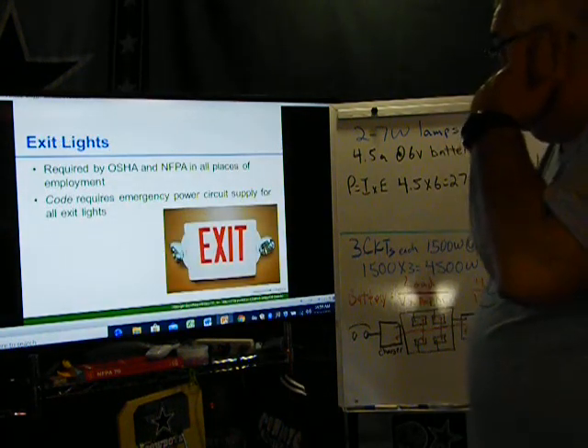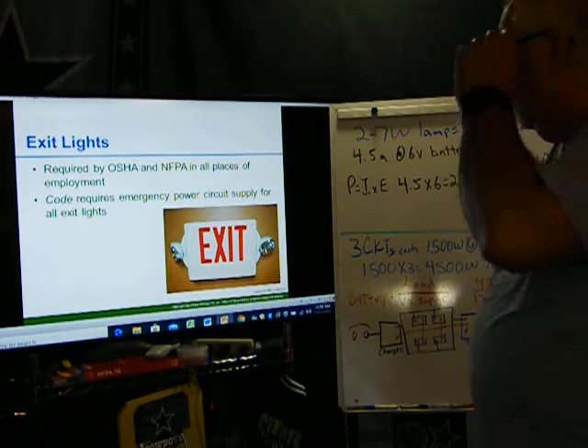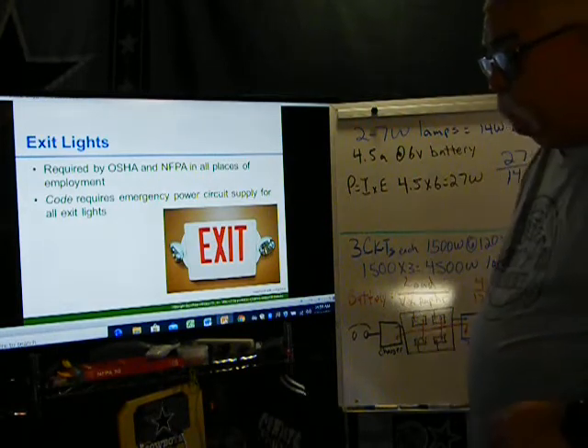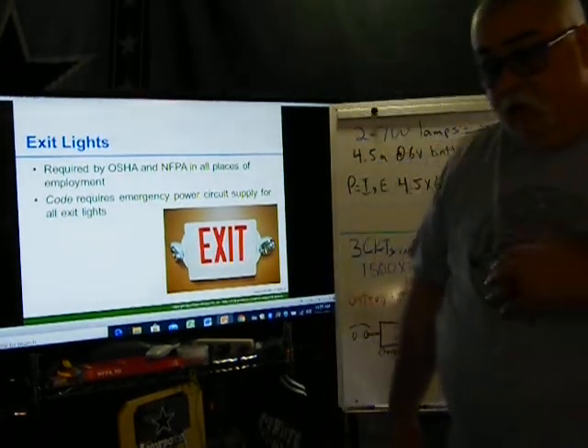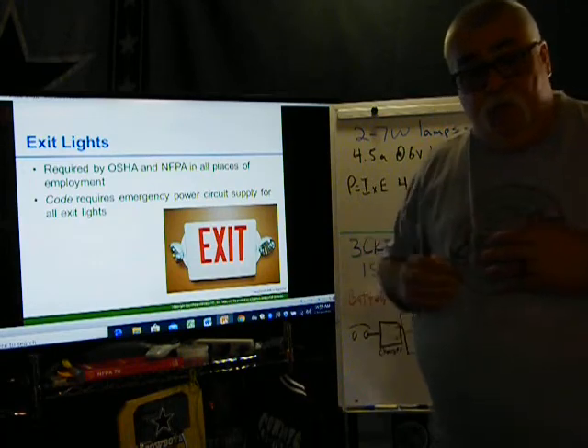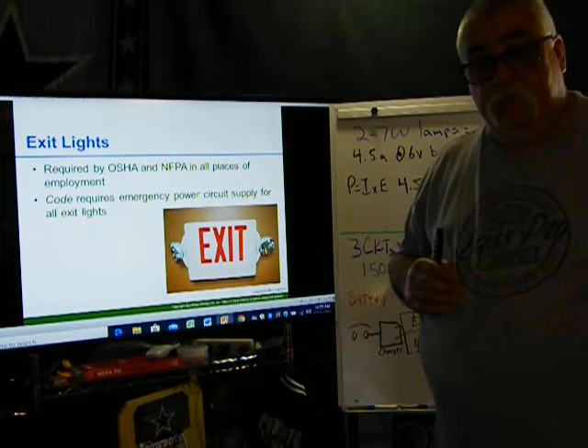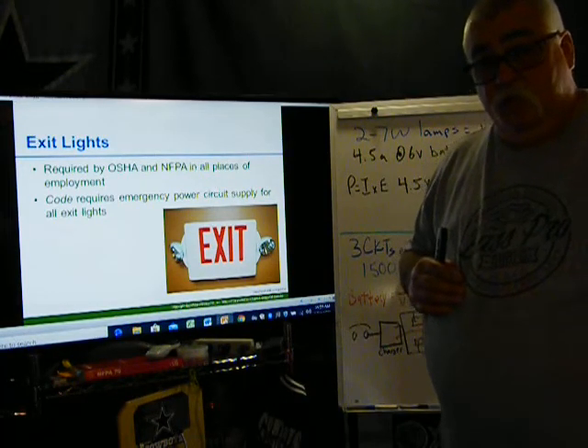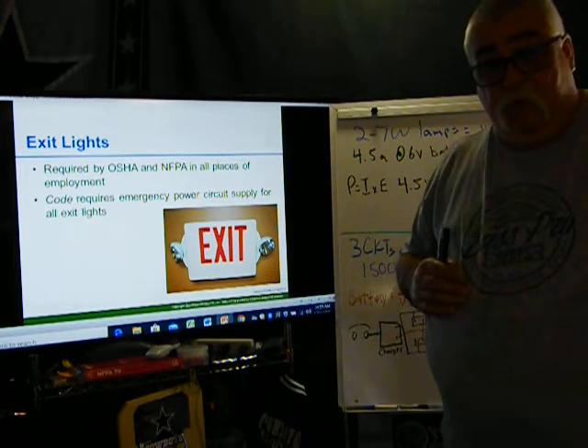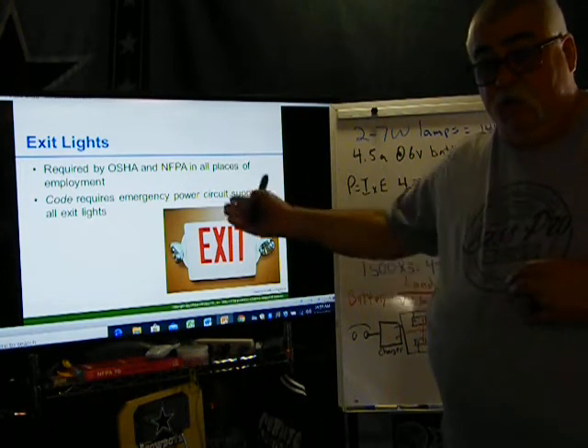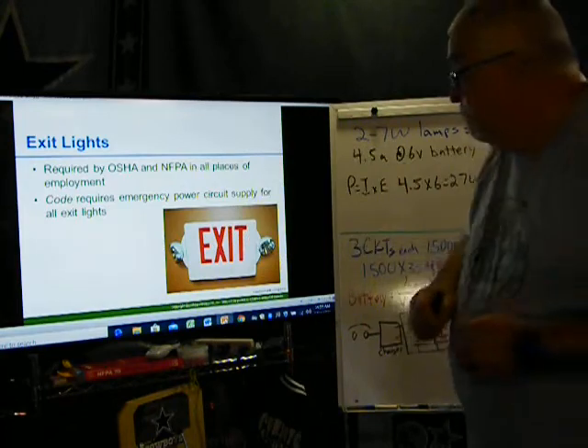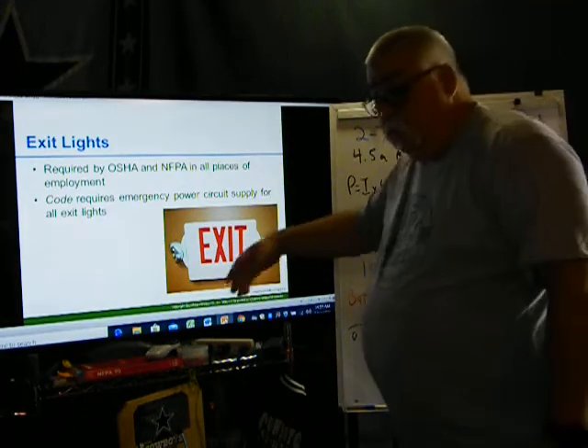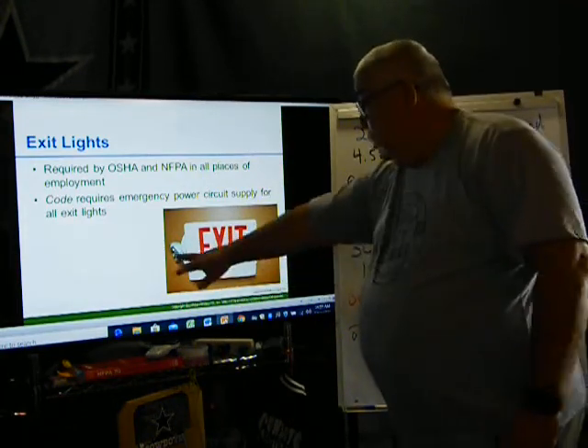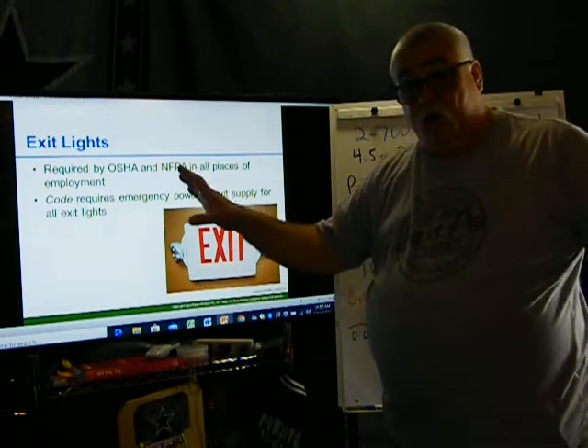Exit lights are required by OSHA and NFPA in all places of employment. If you're exiting a room into a hallway, one, you've got to let them know which way is out, but they have to get out into the hallway. When they get out in the hallway, you need these exit lights to point them in which way. Okay, so here's an exit light. You kill two birds with one stone. You've got an exit light, and it's got the bug lights, so it can light you up.